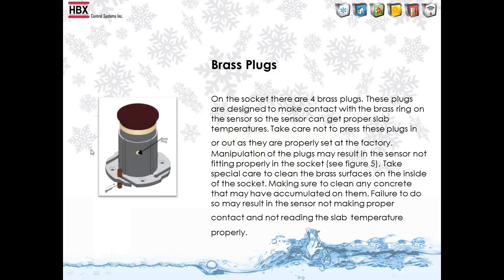When you're installing this, there are 4 brass plugs on the outside of the socket. Make sure those brass plugs are in place, and when you push the sensor down into it, make sure they are pressed in. That gives us contact from the slab to the slab sensor built into the actual SNO-0110 optical sensor. If those aren't touching properly, or aren't in place, then we'll get inadvertent readings on the slab temperature, and the system won't work properly.